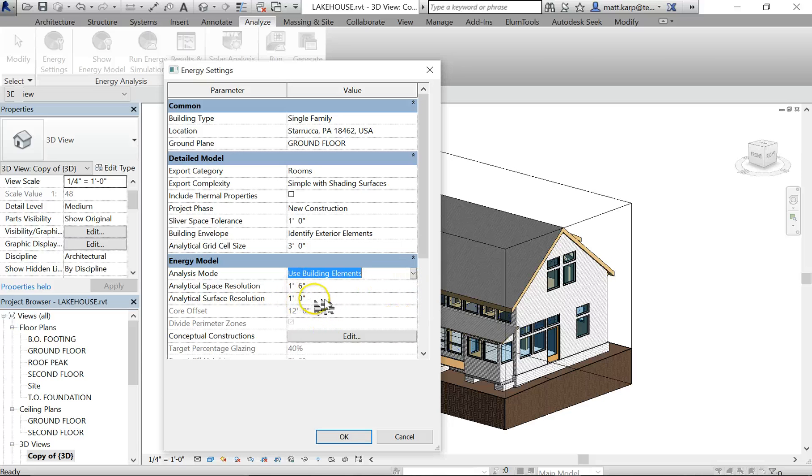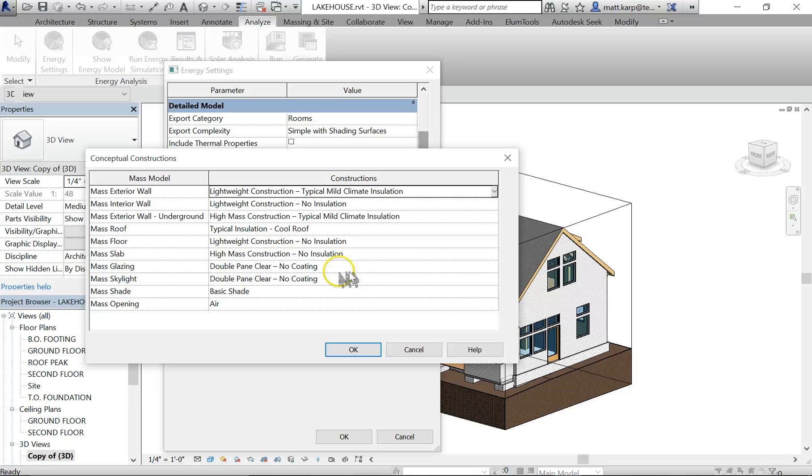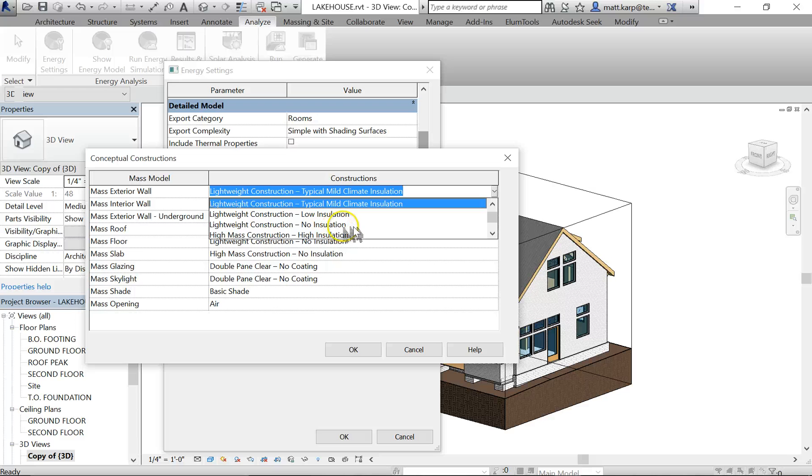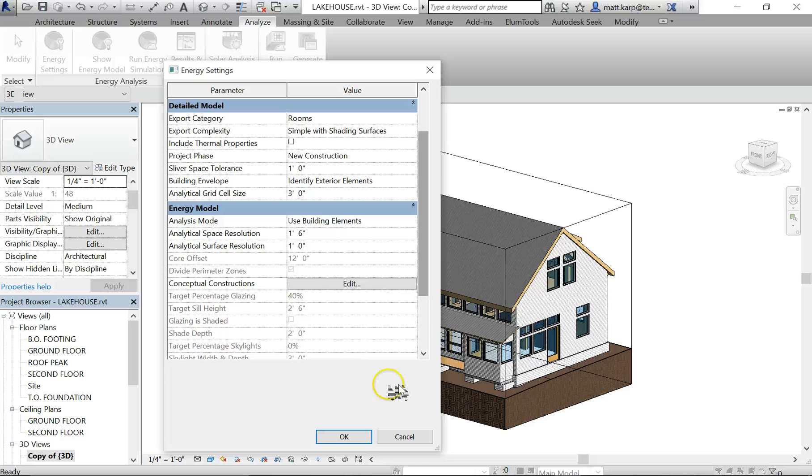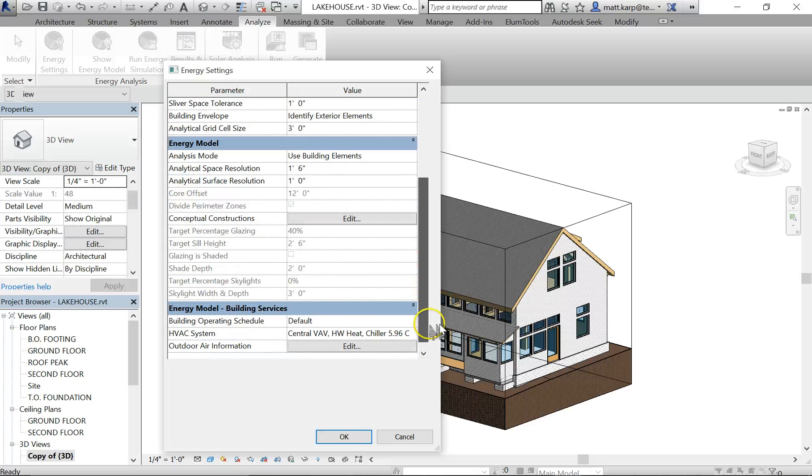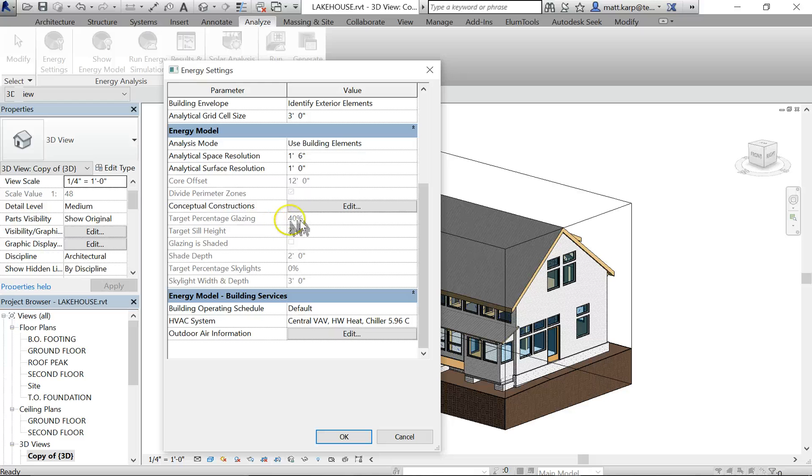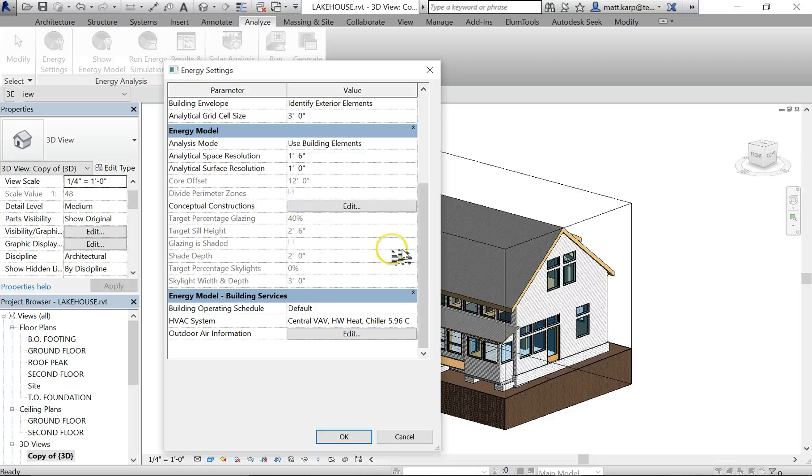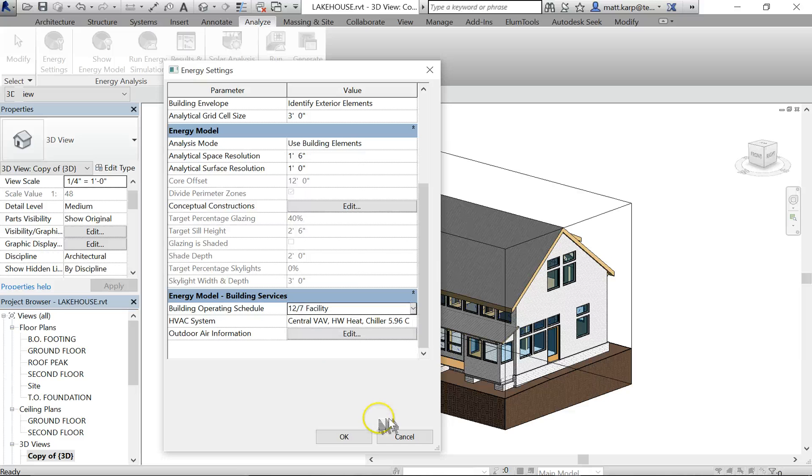We'll leave these as default. If you are testing masses, you will select the conceptual construction, and this has the different insulation types around the project, even your glazing, floor slabs, and your roof. And you can also, if you're testing masses, set your percentage glazing. And what this is, is if you have a big block and you say I want to be 40% glazing, it's going to make 40% of all of the facades you're building glass just for the testing. Set the schedule - this is a home, so it's probably, I would say, 12 hours a day, 7 days a week facility. That's when people are going to be there.